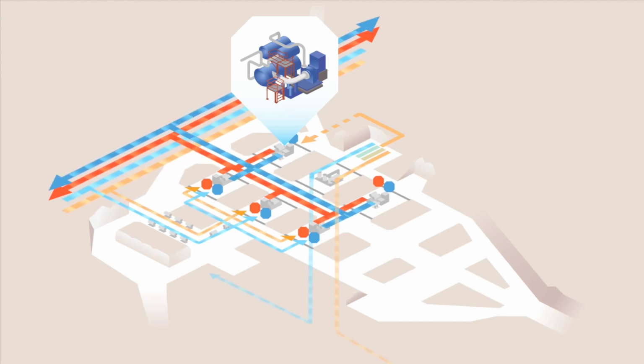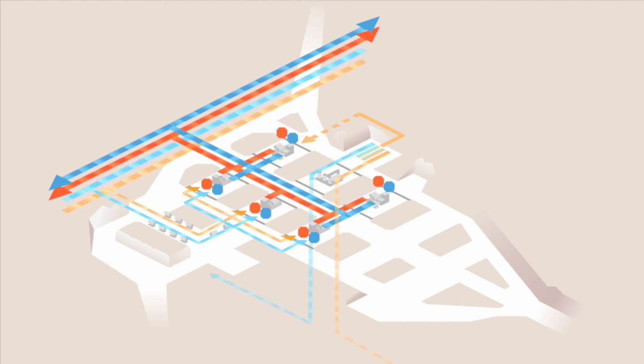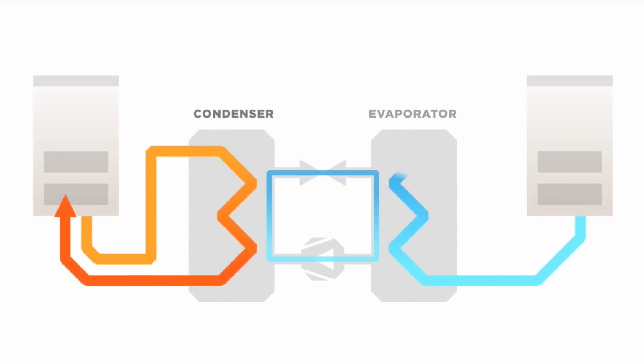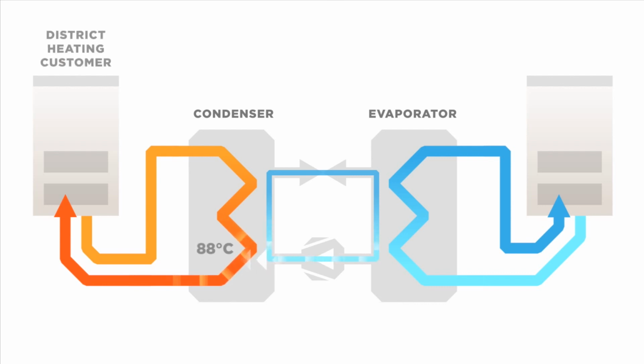The reason why the system is so efficient is that the pumps produce heat and cooling simultaneously. The plant meets the increasing demand for district cooling at the same time as it produces district heat. The key parts of a heat pump are the condenser and the evaporator. The refrigerant circulating in the heat pump transfers energy alternately to the supply water of district heat and district cooling. In the condenser, the refrigerant releases the energy into the district heating return water and heats it to 88 degrees for the supply water for district heating. That way, the refrigerant condenses and returns to the evaporator.